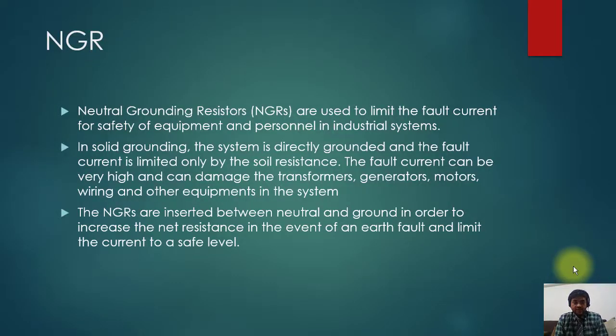Welcome guys, now let's start our new topic which is Neutral Ground Resistor, in short form it's called NGR. Neutral ground resistors are used to limit the fault current for safety of equipment and personnel in industrial systems.